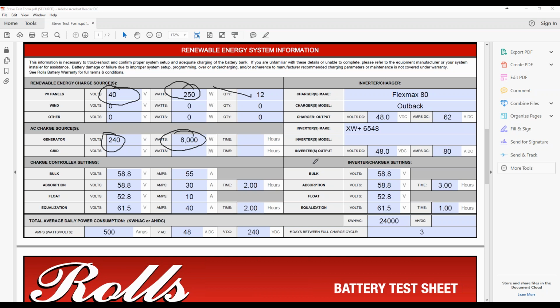Last but not least is the charge controller and the inverter charger settings. This is probably one of the most important things on these forms: your bulk, absorption, float, and equalization voltage, and your average amperage that you see. This is not your maximum amperage, but when the charger is in bulk mode and first starts charging, ballpark where that current usually is. Most customers, especially do-it-yourselfers, can repeat that off the top of their head because they're very aware of what's going on. So just give us an idea what that is. And then, of course, what you've programmed your absorption timers to, or your equalization time. Those are important because most often we find that those are usually too short.